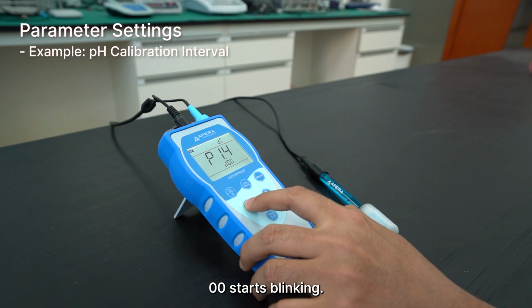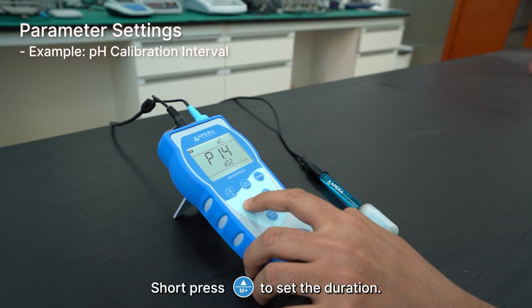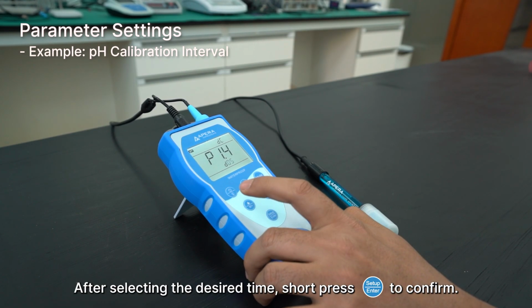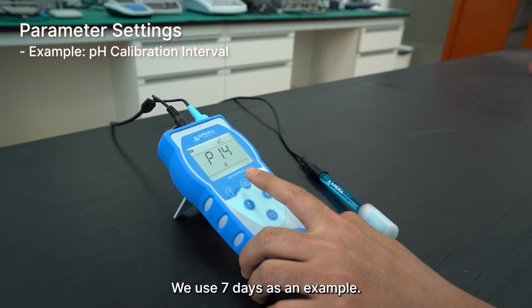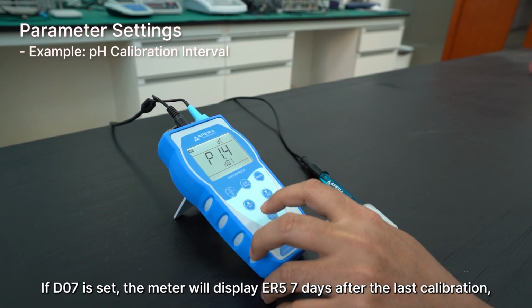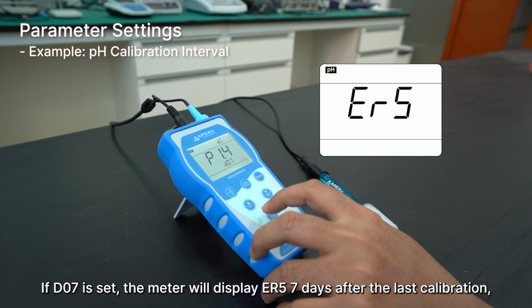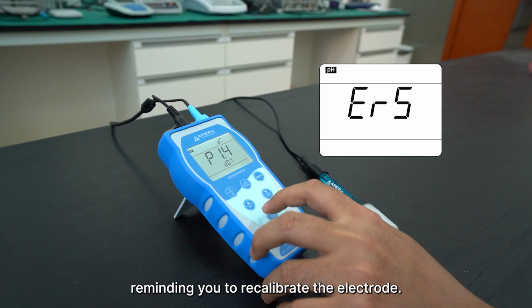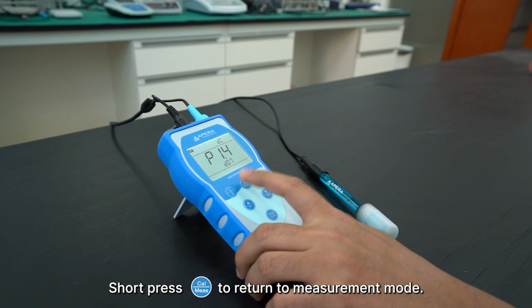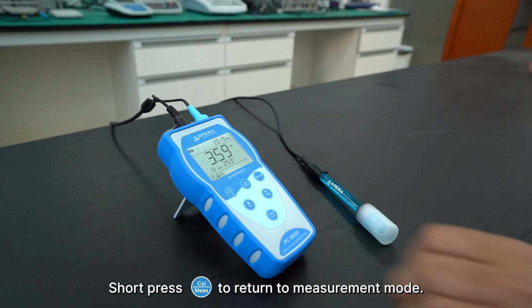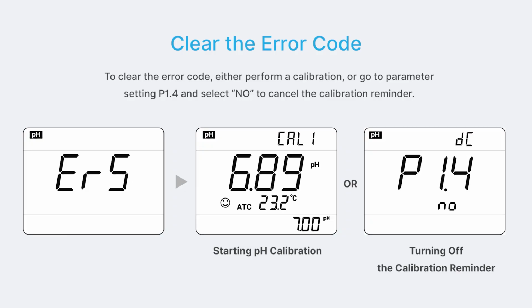00 starts blinking. Short press the up key to set the duration. After selecting the desired time, short press Enter to confirm. We use 7 days as an example. If D07 is set, the meter will display ER5 7 days after the last calibration, reminding you to recalibrate the electrode. Short press Measure button to return to measurement mode. To clear the error code, either perform a calibration or go to parameter setting P1.4 and select NO to cancel the calibration reminder.